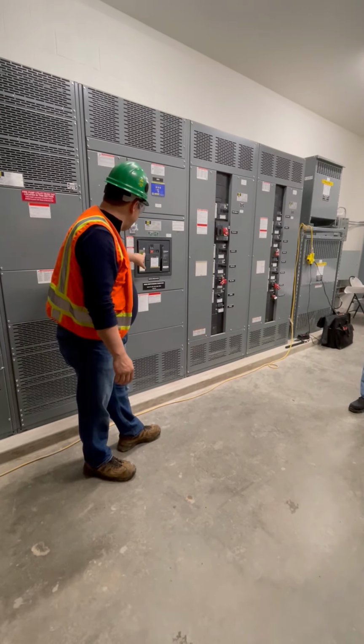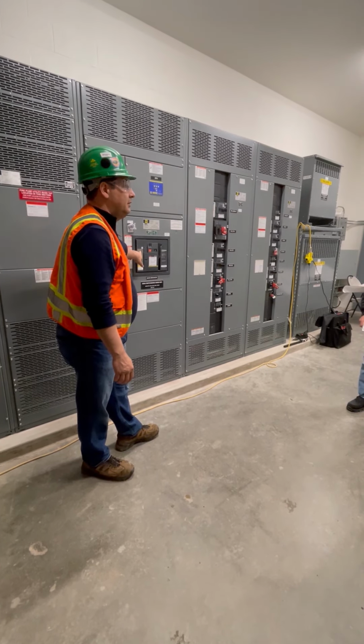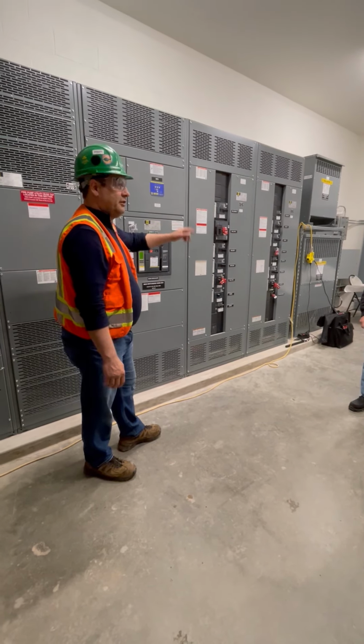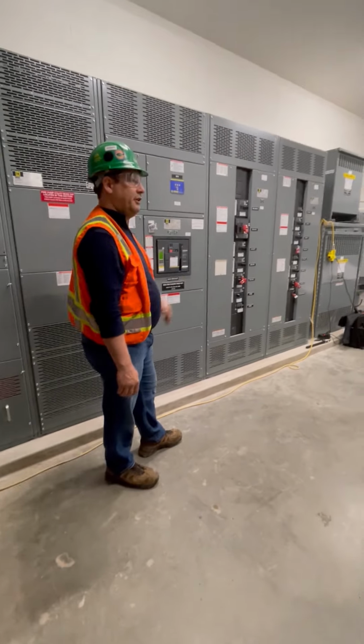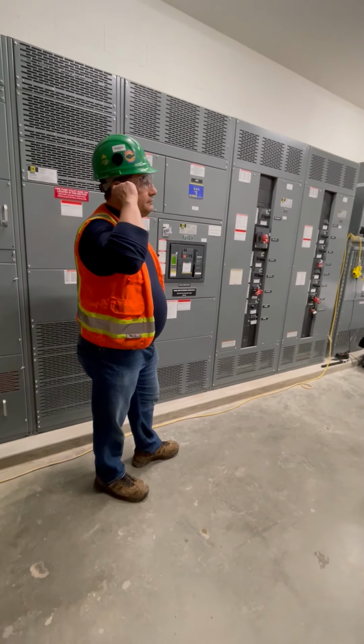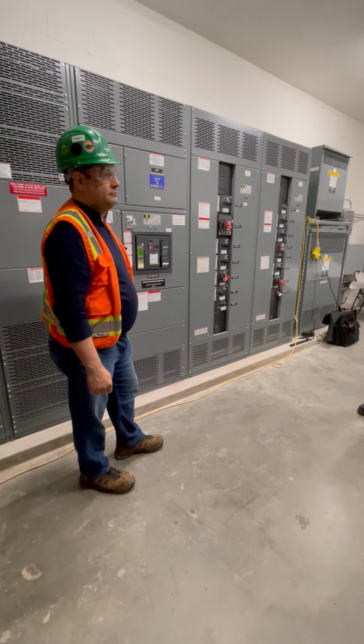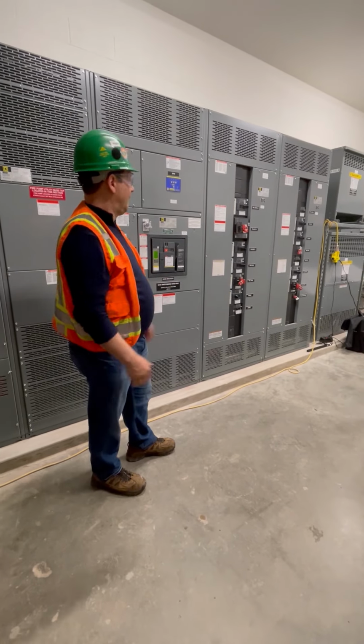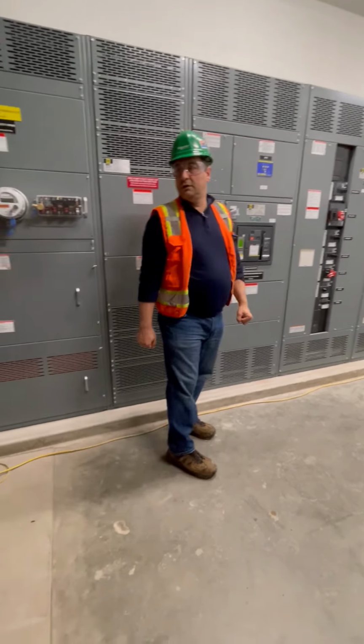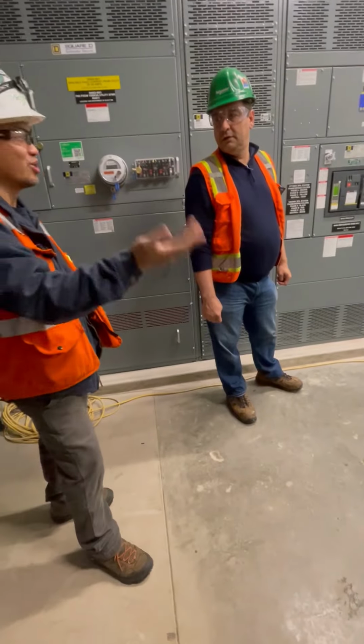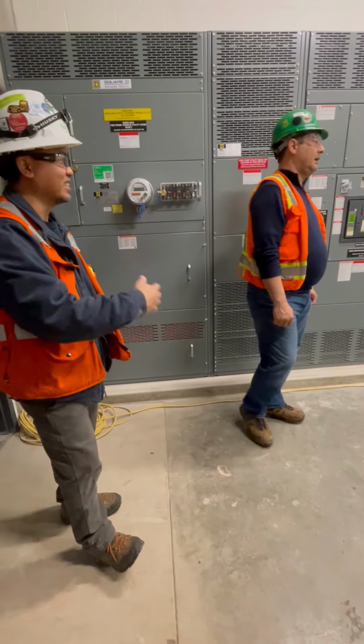But keep in mind, you run out here, you see that ground fault LED is on, you tripped on ground fault, that's when you start the process of elimination and try to isolate it. But we got a generator firing up and everything else happening. Well, if your generator fires up and it starts powering this, it's going to trip again, even if you close it. Doesn't matter, right?